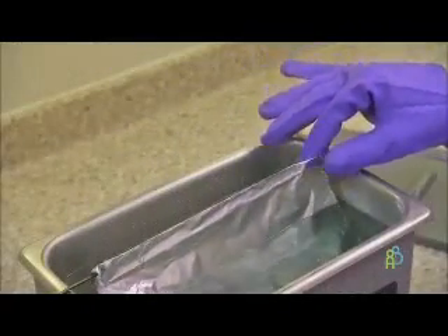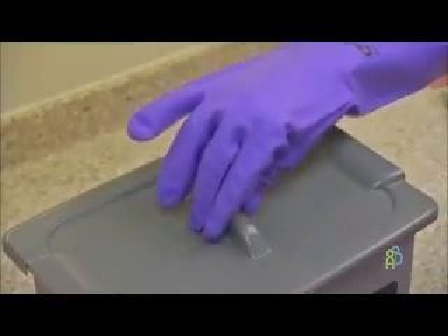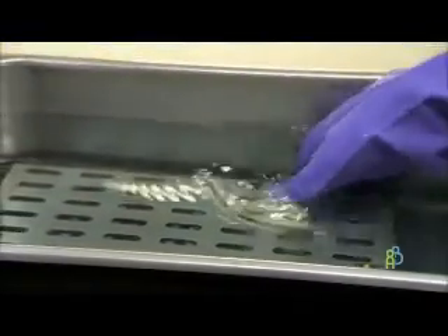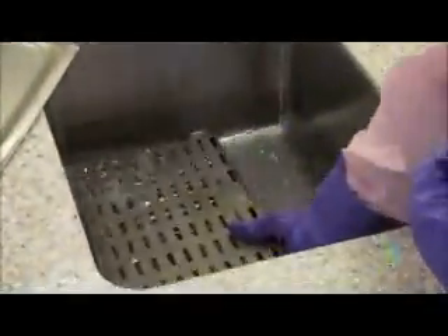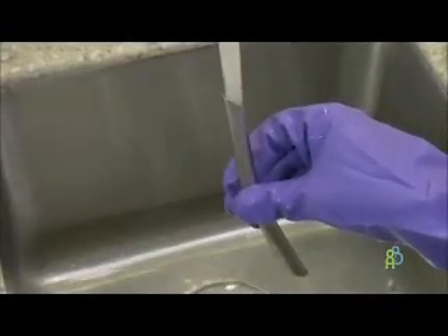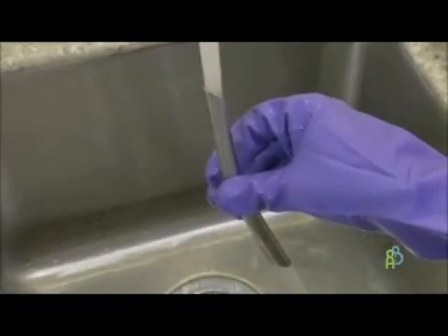The ultrasonic cleaner must be tested for cleaning performance according to the manufacturer's instructions, or at a minimum once a week if no instructions are provided. The results of this testing must be logged. After the ultrasonic cleaning cycle has completed, all devices must be thoroughly rinsed to remove loosened soil. Rinsing must be done using clean tap water and under the surface of the water, not under running water, to ensure removal of all residues and to prevent aerosols. Devices with lumens or channels must be thoroughly flushed following removal from the ultrasonic cleaner.